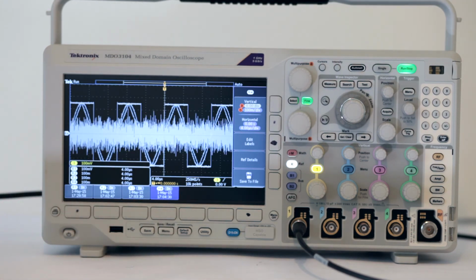You can push Reference Details to get information about the selected reference waveform. Also, using the bottom soft key, it is possible to save the reference signal in an external flash drive inserted into a USB slot. Reference waveforms can be scaled and positioned. Select the desired waveform and adjust with multipurpose knobs A and B.